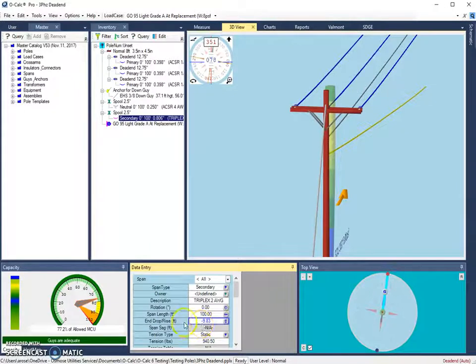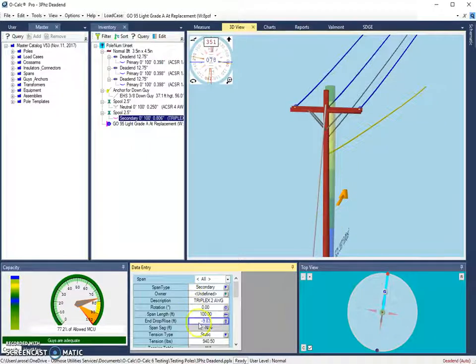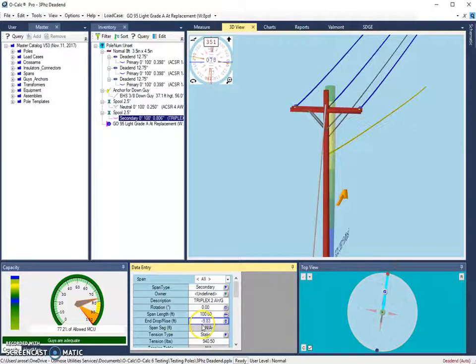So even though that's an above ground line height that we're entering, by entering it in the End Drop/Rise value, it figures out the conversion for us. Your End Drop/Rise is the adjustment that takes place on the other end of the span. So by using the shortcut, it makes it a lot easier than trying to figure out precisely what the End Drop/Rise is going to be.